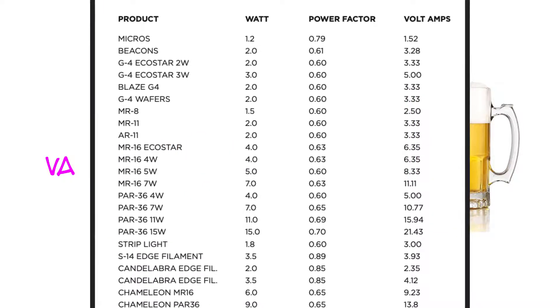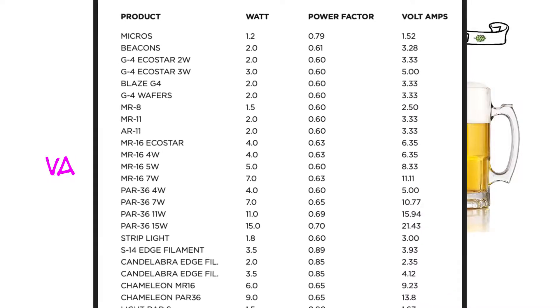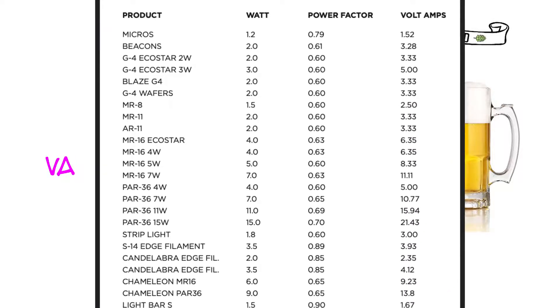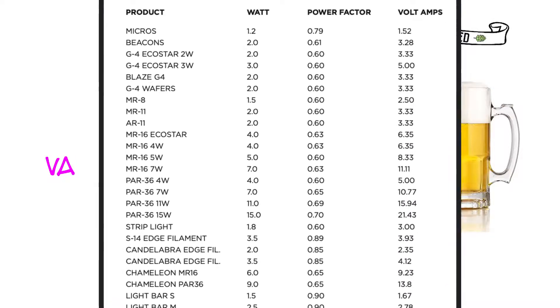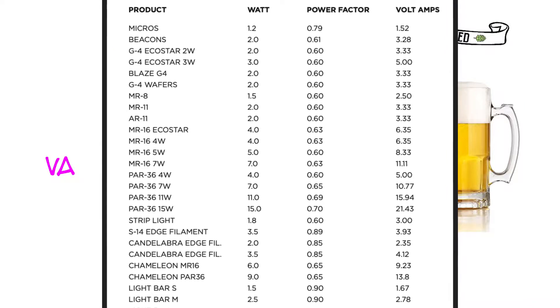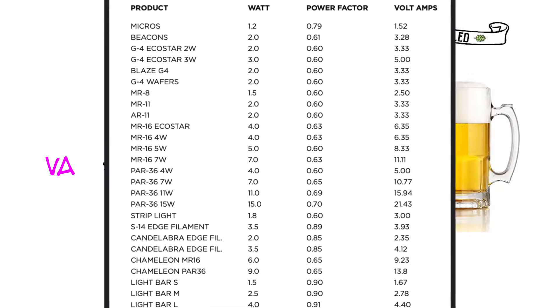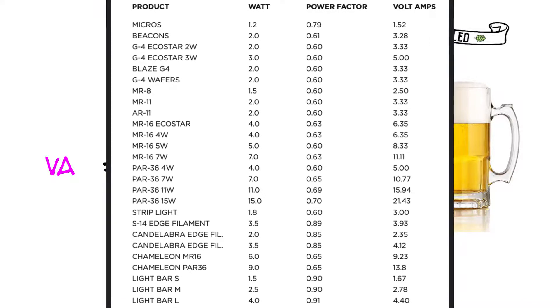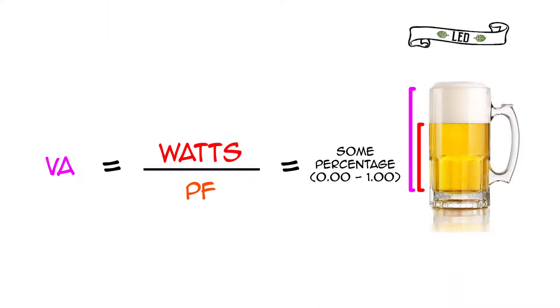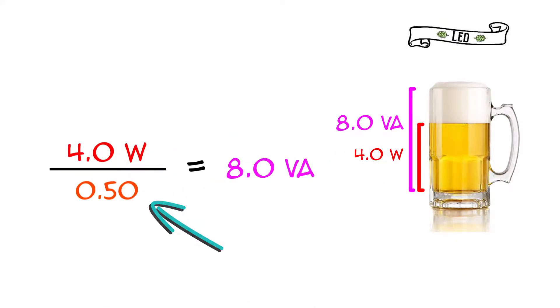Generally, the power factor of LED lamps will be somewhere between 0.5, considered inefficient, and 0.9, considered very efficient. If a lighting manufacturer only provides a watts figure, we recommend assuming a low power factor of 0.5 to be safe.